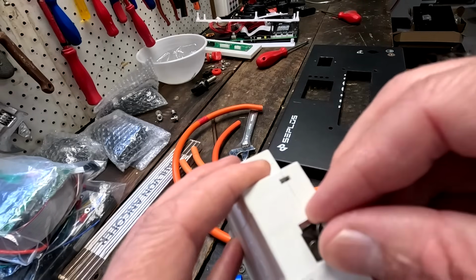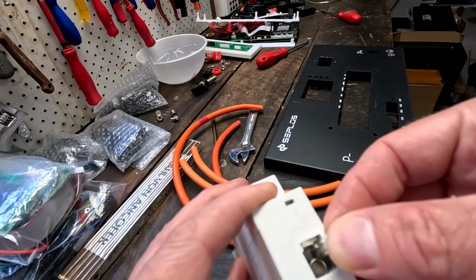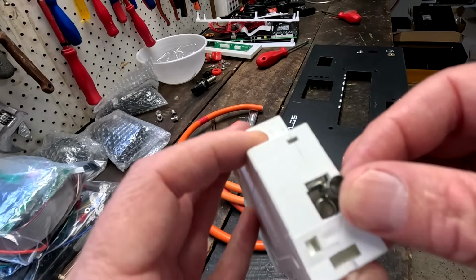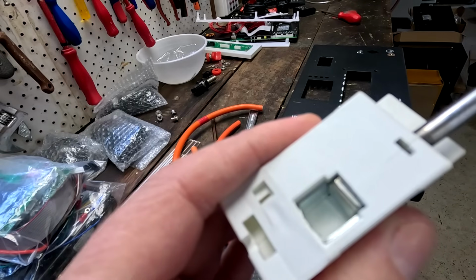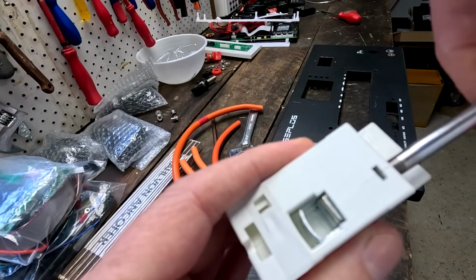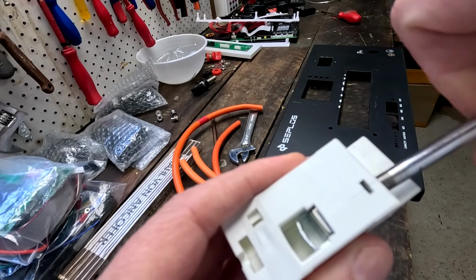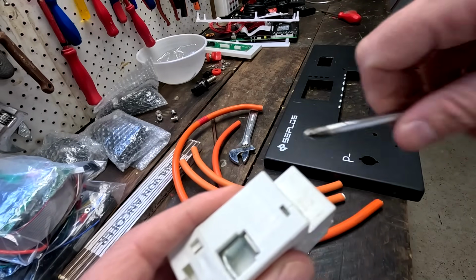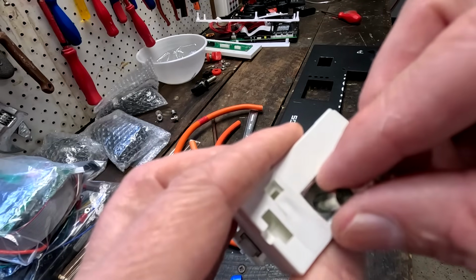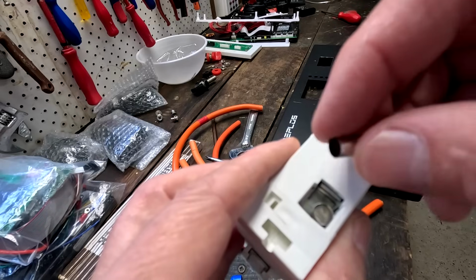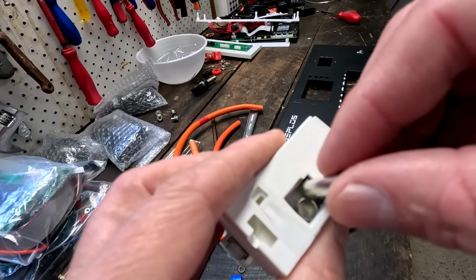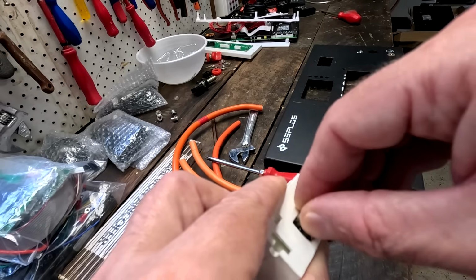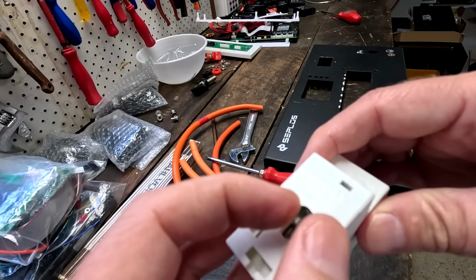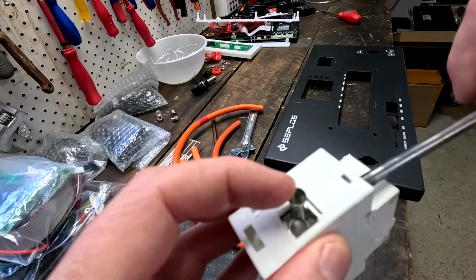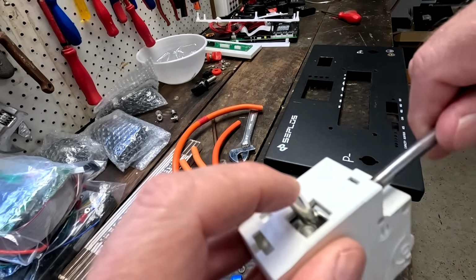But once they are crimped, they are not round anymore, and we should be able to get 2 of them in here. With this kind of terminal, we don't necessarily need bootlaces, but I'm still a big fan of them. They keep all the strands together, and if you need to undo the cable, it's all clean and you can get them into the terminal again without any issues. I may try that first, and if it doesn't work, we go without.